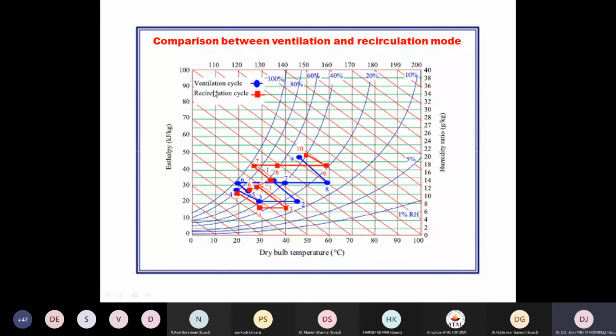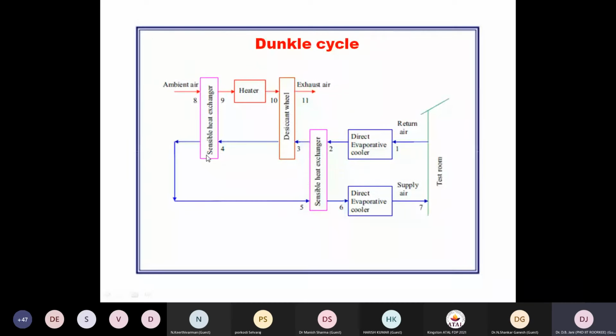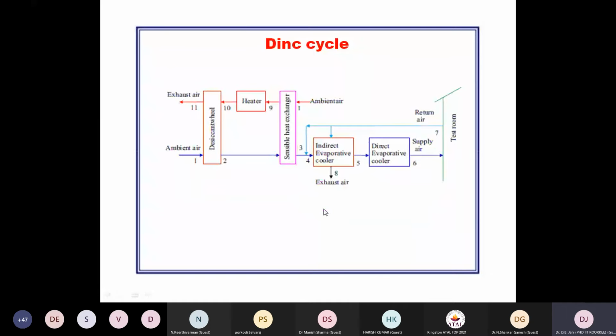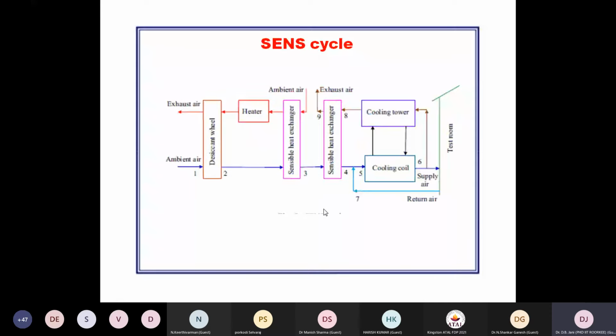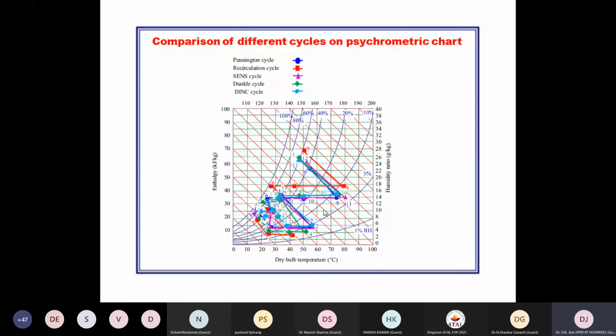So how can we compare the two systems on the psychrometric chart? From the comparison, we may find certain benefits: the red recirculation cycle can drop the temperature to the lower desired value, while the ventilation cycle has a requirement of a lower regeneration point compared to the recirculation system. In the Dunkle cycle, there is incorporation of more than one sensible heat exchanger, and a couple of direct and indirect evaporative coolers. The Sense cycle uses a cooling tower and partially splits the cycle to supply air for reactivation in the middle. We will also make a comparison of the different desiccant cooling cycles on a common scale on the psychrometric chart.